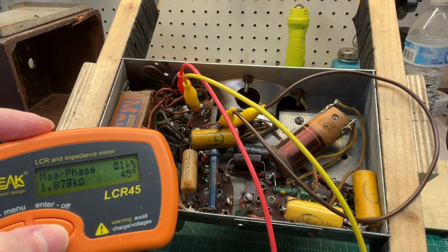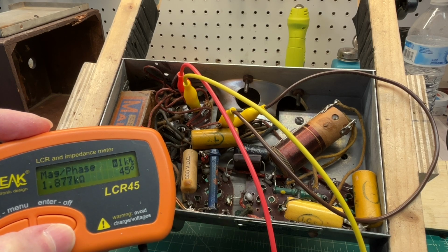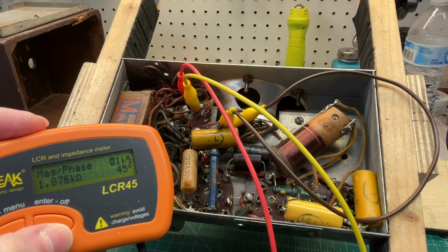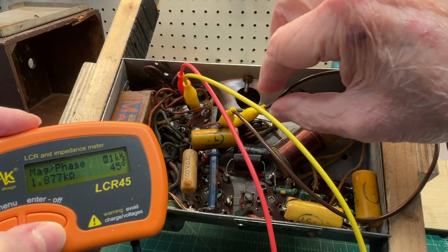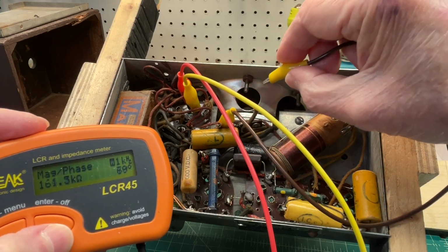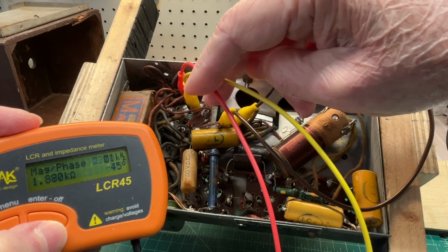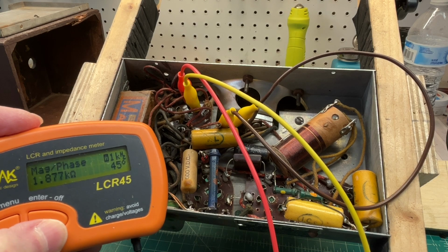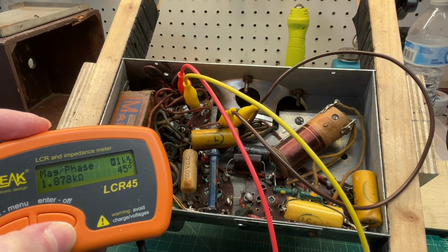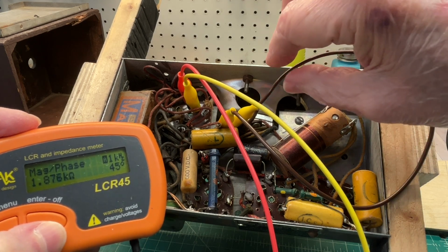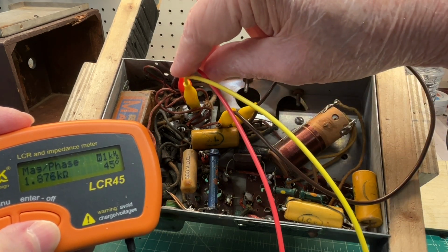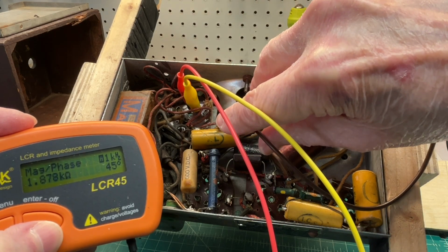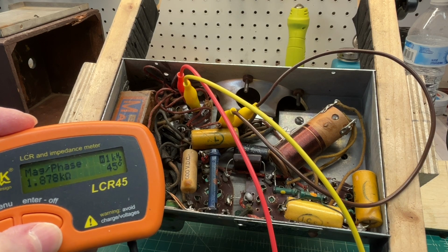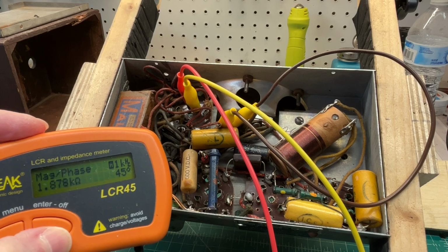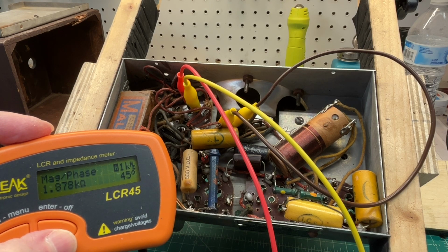Another method and procedure I've shared in the past is how to use the LCR45 meter and look at the magnitude phase of the transformer when checking leakage inductance. I'm shorting the primary side of the transformer and reading the high voltage winding across the entire winding, plate to plate. You can see, for note, 1878 ohms of resistance. Now I'll swap and place the short on the high voltage winding, then read across the primary and record those measurements. We'll do some math and use those numbers to extrapolate the number of turns for the transformer, as well as the voltages for the high voltage side and the secondaries.